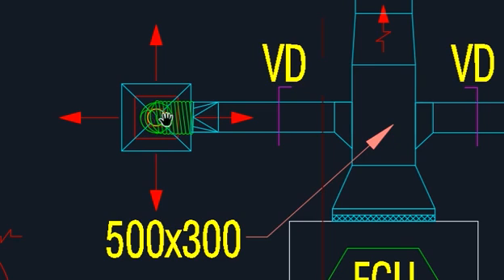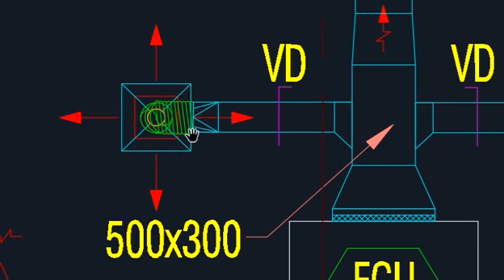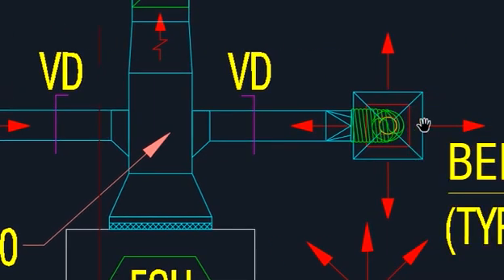The flexible will be connected to a connector here, and that connects to a plenum box — also called a diffuser box or acoustic lining box. This is like a box, and inside, acoustic lining — a special cloth or foam — is wrapped inside. This is because the air coming in from the flexible duct still generates some sound, and the acoustic lining inside the plenum box eliminates that sound. So the air enters the plenum box with acoustic lining inside and goes out.